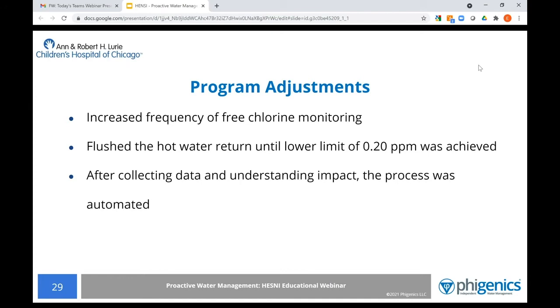This is due to cross-contamination, which occurs because in our fixtures, the hot and the cold water flow through the same outlet point. Once we confirmed the success over several quarters of testing, we then automated the flushing by installing a solenoid valve and connecting it to our building automation system. This allowed us to flush automatically at a prescribed time duration. So we do it on a time duration that was set by our previous manual flushing and chlorine residual testing. Again, we did some manual flushing, we had some success, and then basically automated it to reduce the manpower required to do that flushing at the hot water return.